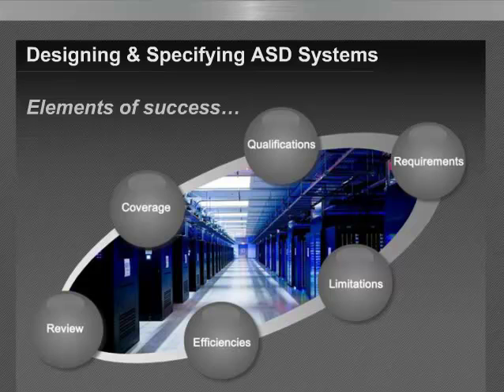Apply coverage techniques that will account for all possible smoke migration paths, as we've touched on in some of the illustrations, never exceeding limitations specified in product data sheets or design guides. Maximize coverage by utilizing combined coverage techniques where possible, and that is potentially utilizing the detector to monitor multiple points where it has the capacity. Ensure the system design meets the manufacturer's criteria, local jurisdiction requirements, and include the manufacturer in the early stages of project work.